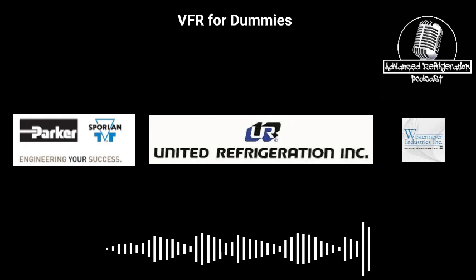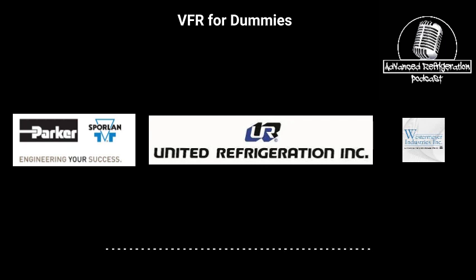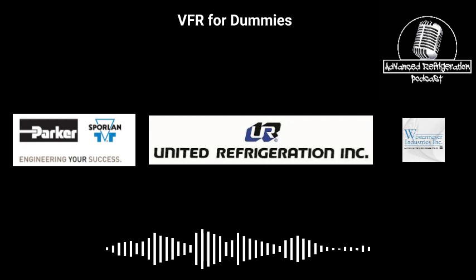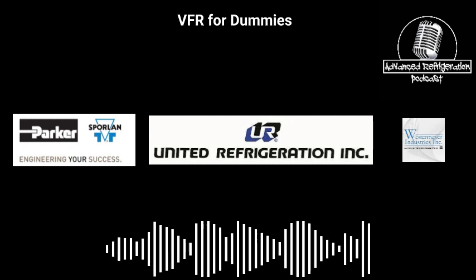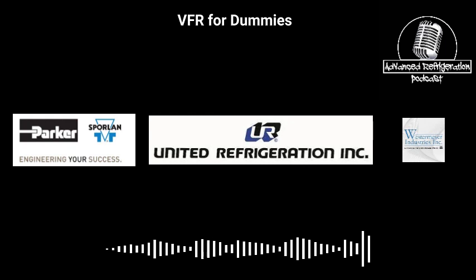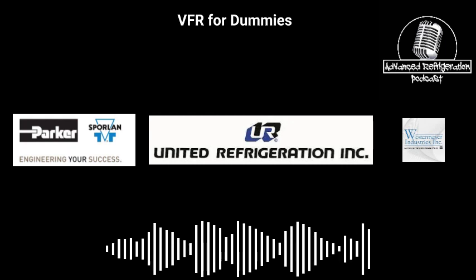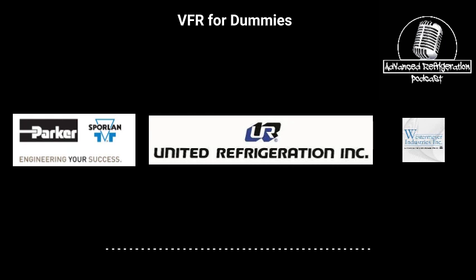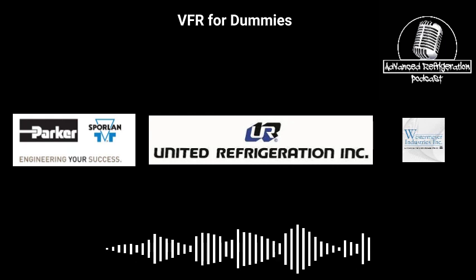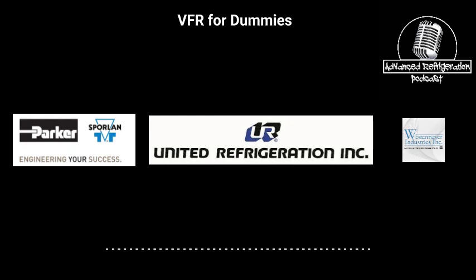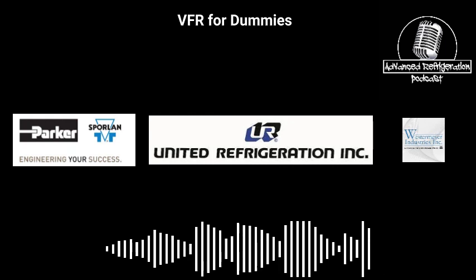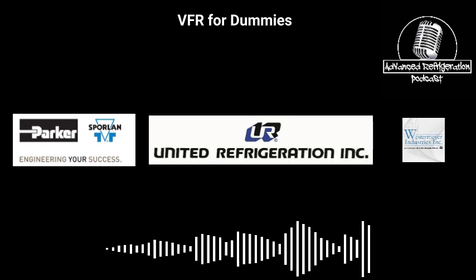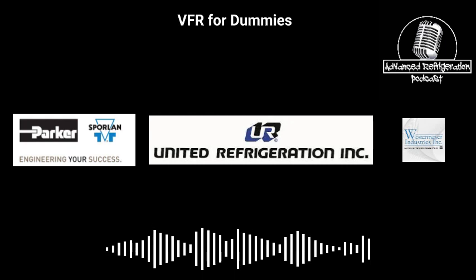So how do you know what the branch box is supposed to be doing then? Hoping and praying that if it's in heat, you get heat. If it's in cool, you get cool. And that gets that signal from each fan box out at each room, right? Yeah, because that's going to tell it what flow to have, right? Correct. Yep. That's going to basically control that expansion valve where there were two kind of stacked on each other. Yeah. Whether we open the suction valve or the high pressure, low pressure. Yeah, but they're basically just opening up or closing. There's no real modulation going on with those.